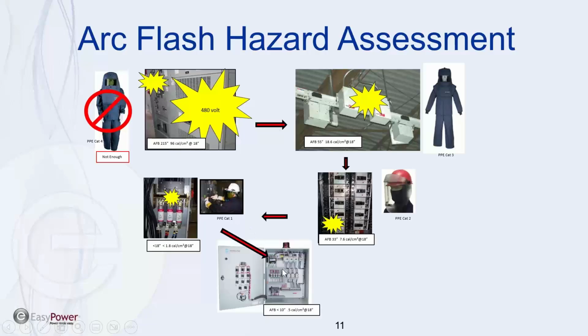Downstream, we are into the control cabinet area, and it's at a very low level, 0.5 calories. So with cotton clothing and plastic rim glasses, of course, arc fleet rubber gloves are rated for arc flash and shock, so that's covering up close arc flash. That's another thing that people don't think about.